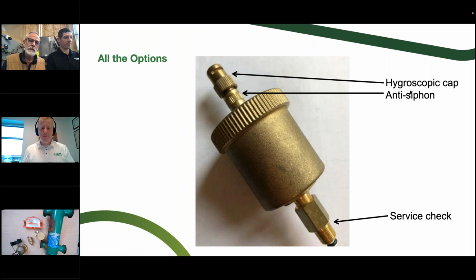That's pretty awesome. And you'd want to be careful if you use a gauge cock, an 1/8 inch gauge cock, because I'll show you on our 1/8 inch vent, most of the vents have a little tab on the bottom of it. And that little tab, when you put it in the air scoop, goes down into the flow a little bit. And I found if you screw that into a ball valve, sometimes that'll hit the ball in there, and then obviously it won't work. You won't be able to turn the ball valve on and off. So be careful with a gauge cock. It's better to use that service check than trying to screw that into a little mini ball valve, for example.